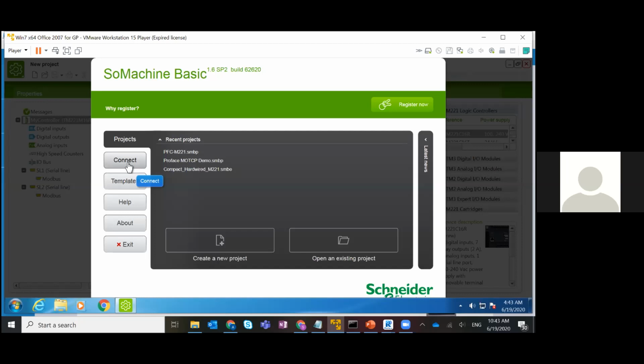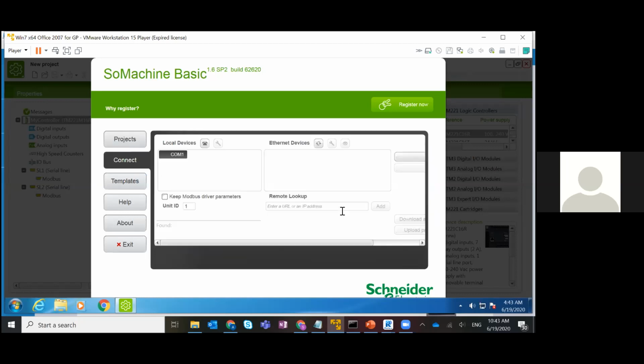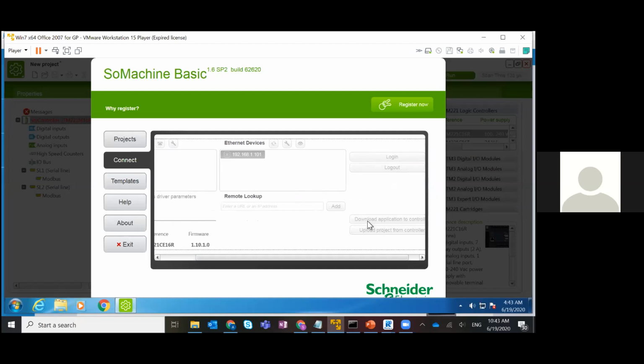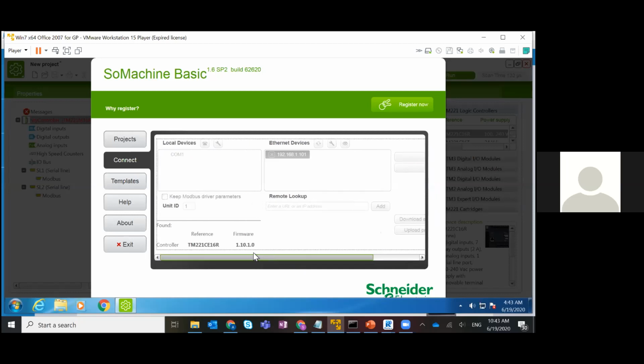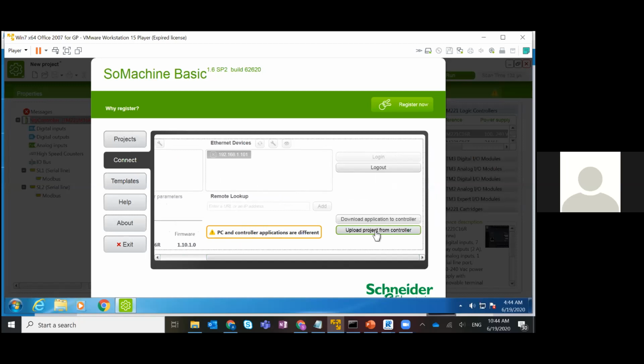So using the PLC software, I can connect to the PLC. This is the IP address of the PLC, as you can see it's a local area network IP. All I need to do is log in. After I log in, I can see information such as the firmware and the reference number of the PLC. I can upload the project from my controller.